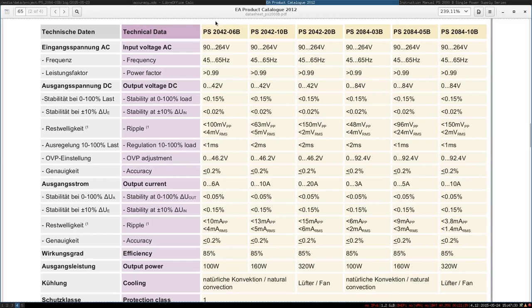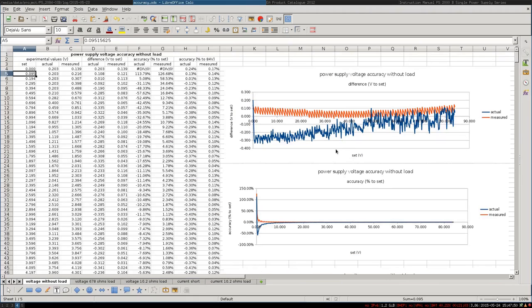If we look at the data sheet, this is from the EA product catalog 2012. We have the PS 208403, and you see here that the accuracy for the voltage should be less than or equal to 0.2%. If we look at these values, this is not the case at all - it's not less than or equal to 0.2%.